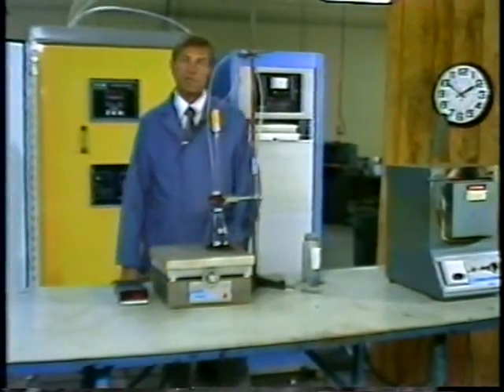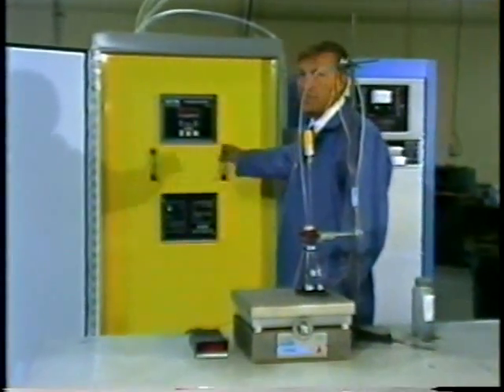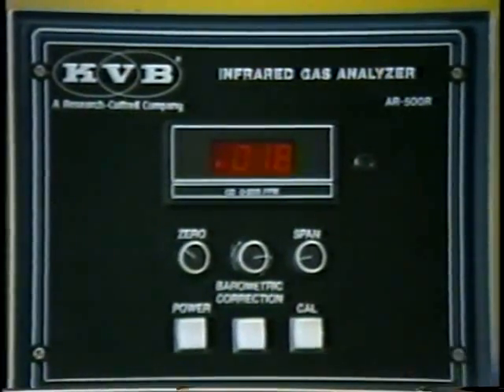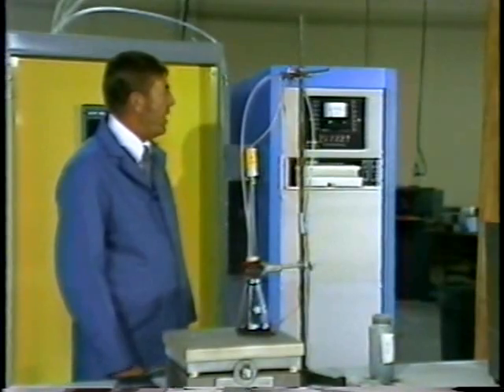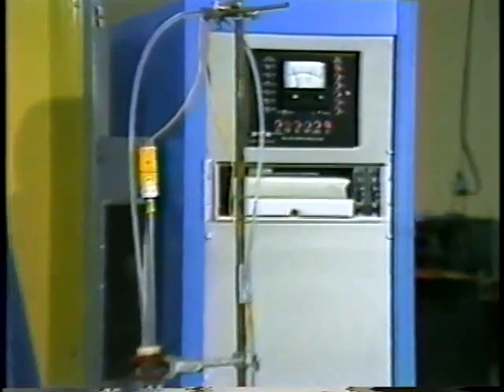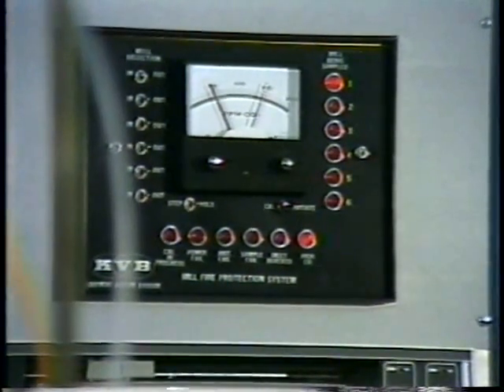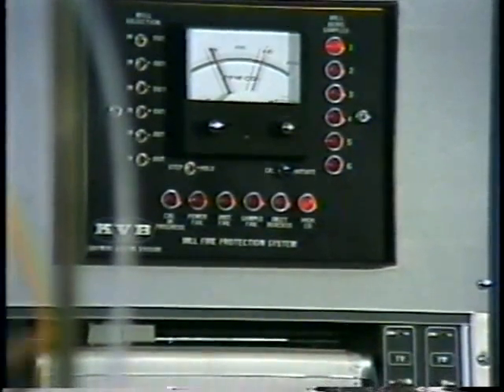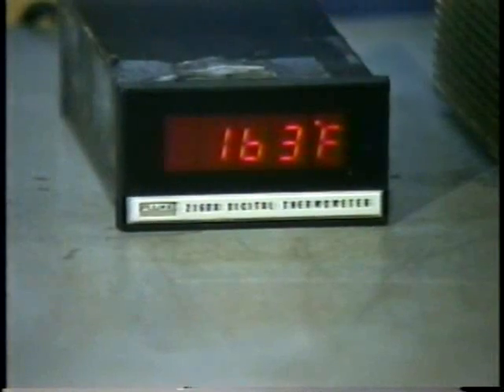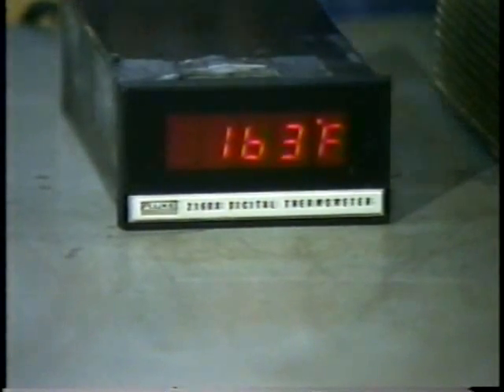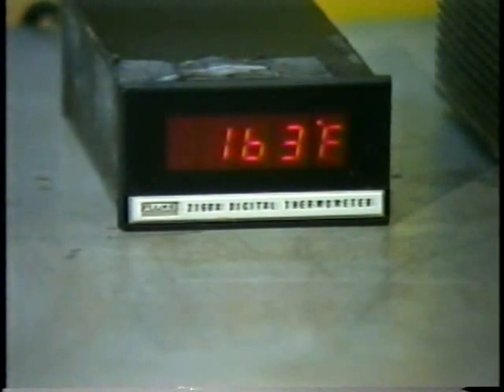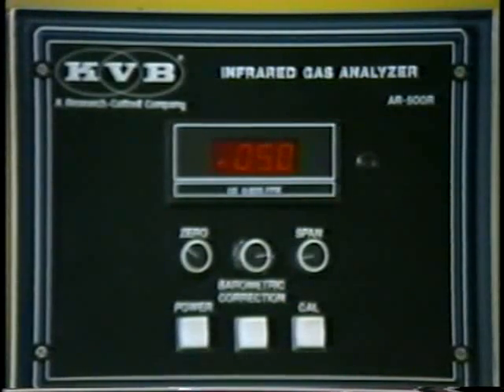After approximately 2 minutes, the first indications of oxidation are visible on the CO analyzer. After approximately 4 minutes, the high CO alarm is showing on the coal fire protection system. After approximately 5 minutes, the temperature is still approximately 163 degrees Fahrenheit, while we're showing approximately 50 parts per million on our CO monitor. The report examined methods for giving advanced warning of fire or explosion hazards.